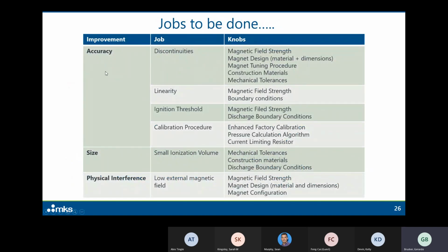So the jobs to be done, as we looked at the cold cathode gauge technology: we had to work on a gauge design that was free of discontinuities, that had good linearity, and a lower ignition threshold below the 10 to the minus 8 that we wanted to measure. We also knew that to get the accuracy, we were going to have to work on an enhanced factory calibration procedure, and very likely revamp the way in which we did pressure calibration. We also knew that we had to push the envelope of how small we could go with the gauge, and that we had to keep the external magnetic field really low.